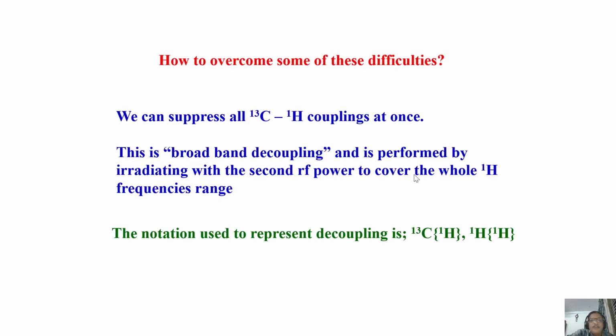Apply an RF pulse in such a way that it has a wide range of excitation profile. The RF power of the pulse must be applied so that the excitation profile is broad and at the same time has uniform power.